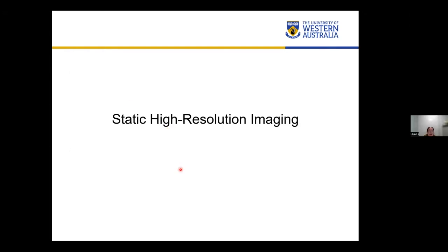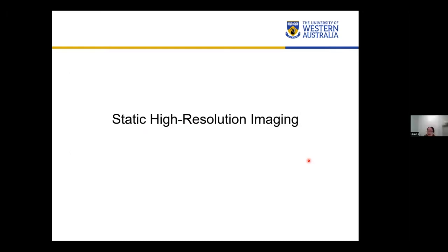A question arose about whether the video rate AFM uses the same tips as normal AFMs. This AFM has two modes. In conventional mode, it uses the same types of tips as other AFMs. For the high-speed mode, it has the ability to use very tiny tips, which are about 10 micrometers in length, to measure the surface so as to reduce noise and oscillation.